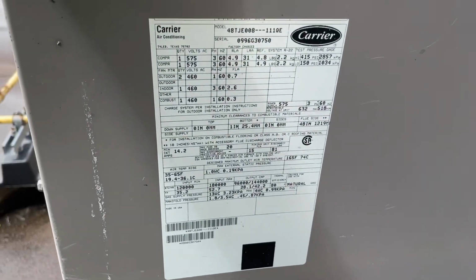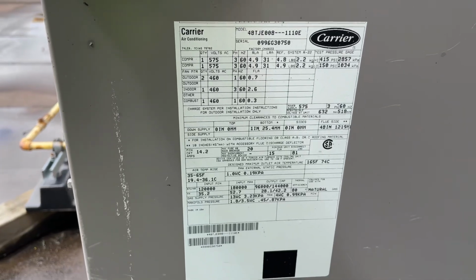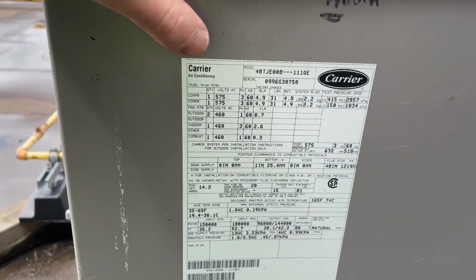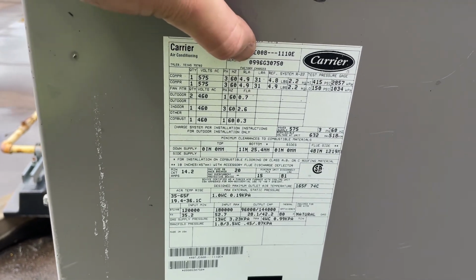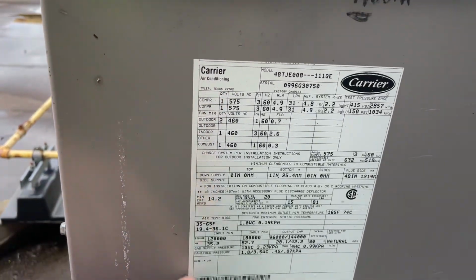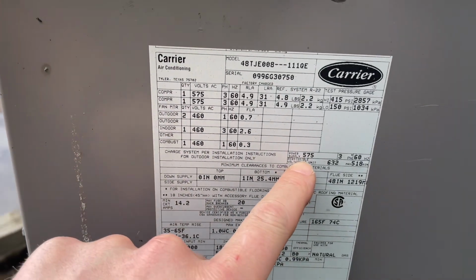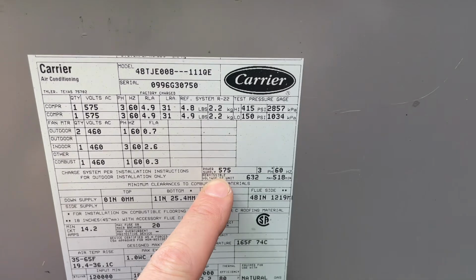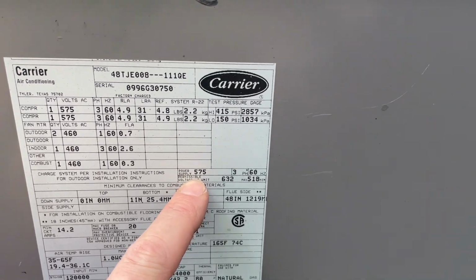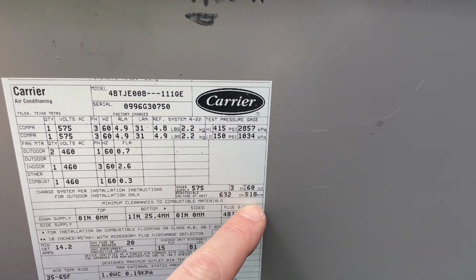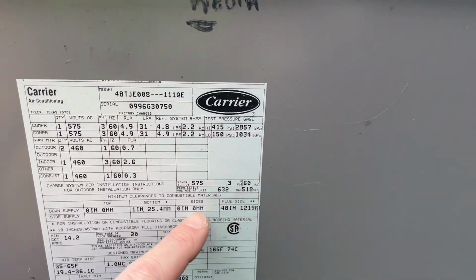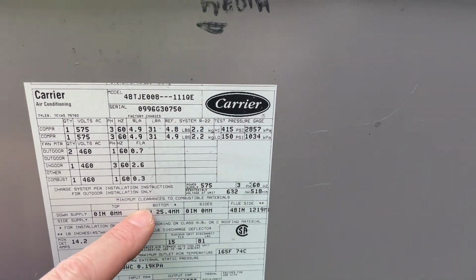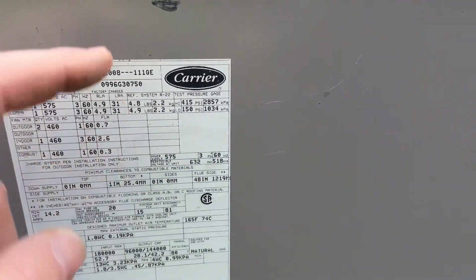All right, so the next thing you guys are gonna wanna look for is your rating plate on your machine. This unit here is a Carrier. This is your model number, serial number, gives you motor specs. Most importantly here though, you're gonna wanna find your power supply. So we know our unit is 575, 3-phase, 60 hertz. That's very important. You don't wanna have the wrong voltage unit come crane day.